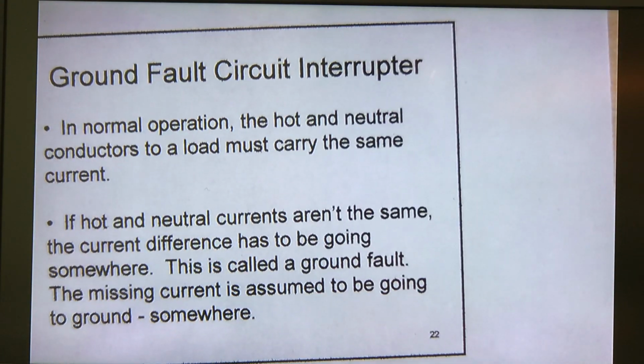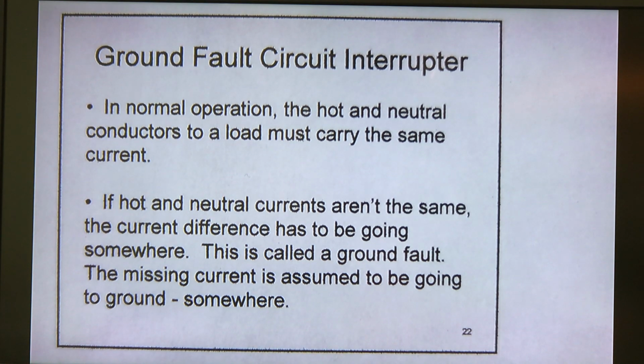Okay, and last topic, and this will be new material, and so at least for this semester, it's not on the quiz for the ECN 4024 group. We also have ground fault circuit interrupters. In normal operation, the hot and the neutral conductors to a load have to carry the same current. Mr. Kirchhoff says that what goes in comes out, and that's what this means. So if everything is connected and operating properly, if your hot lead is carrying 3 amperes, then your neutral should be carrying 3 amperes. The ground should not carry any current. It's all between hot and neutral.